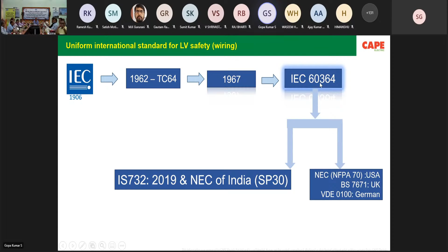Now, when it comes to low voltage electricity, the National Electrical Code of India is originating from the international standard called IEC 60364, which is followed worldwide. For example, the National Electrical Code of America, British Standard, Indian IS 732, all these standards are made based on the uniform electrical safety regulations, or the standard called 60364, made by the IEC.